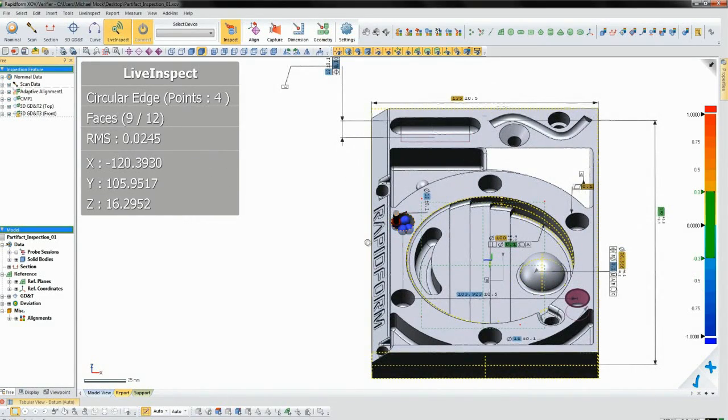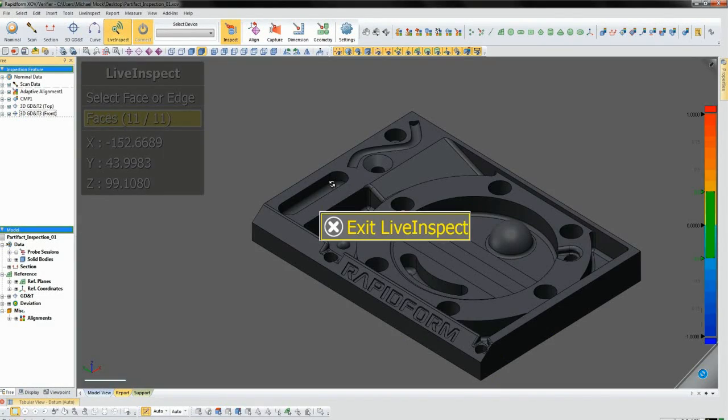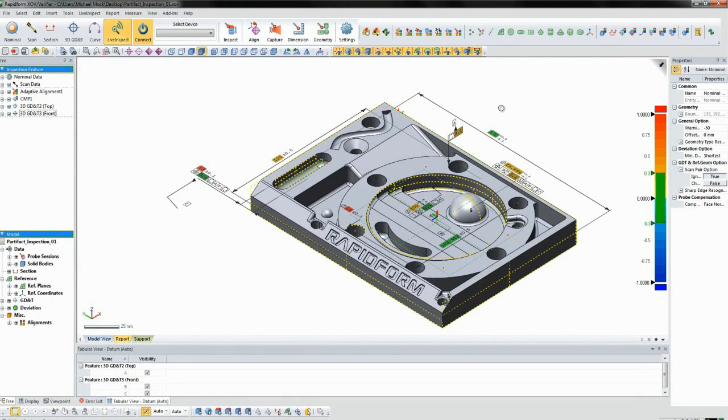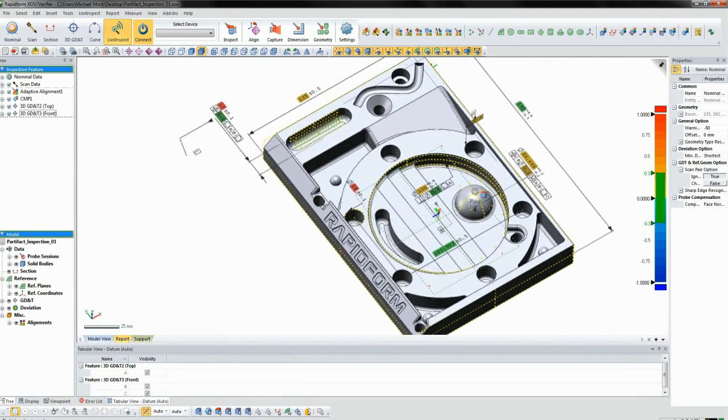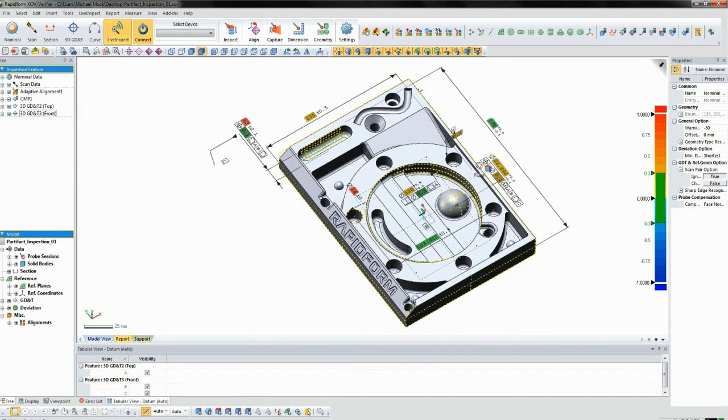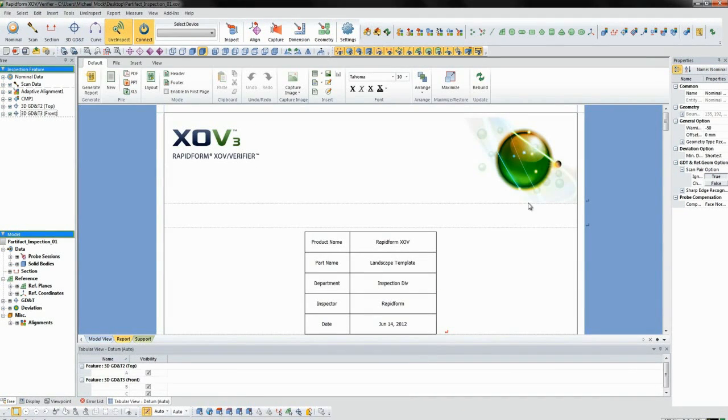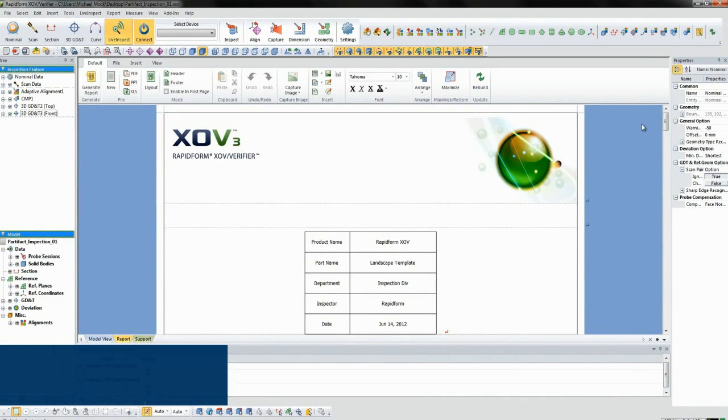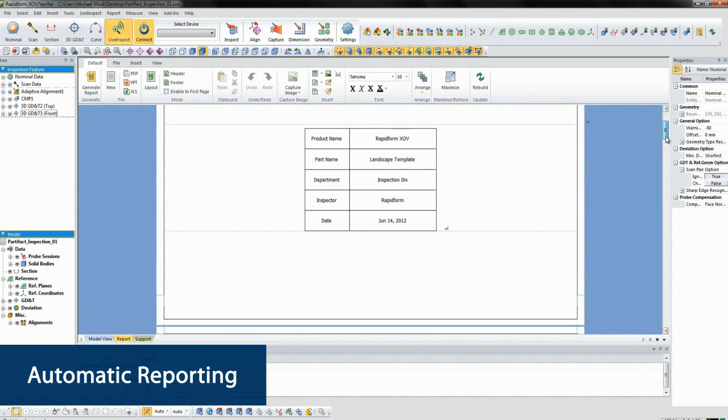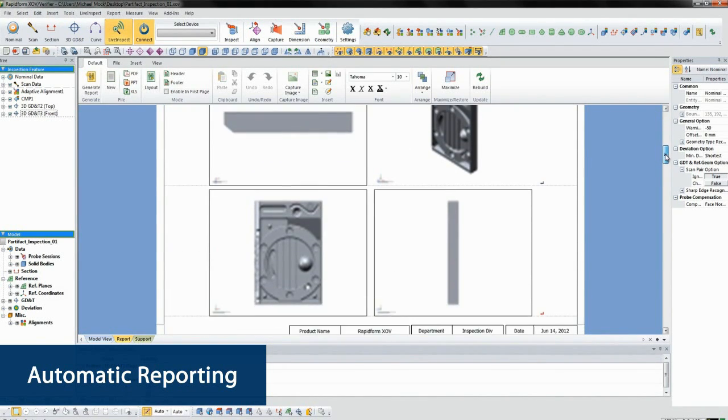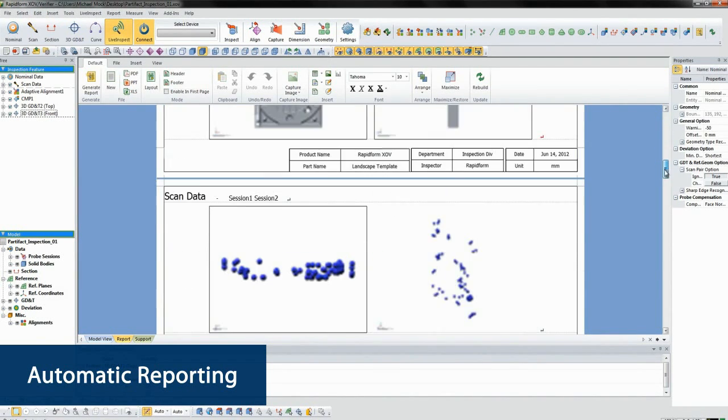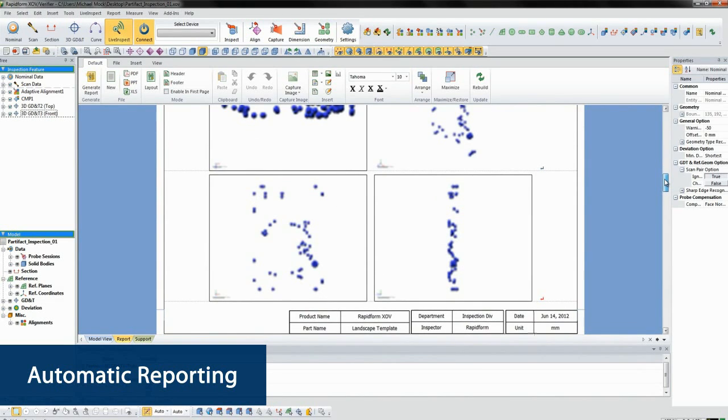Once we've measured everything, we can exit Live Inspect, again without touching the mouse. XOV has already generated a report in the background based on a configurable template. If we click the report tab, we can see the report with the measurement data and the dimension and tolerance results nicely laid out.